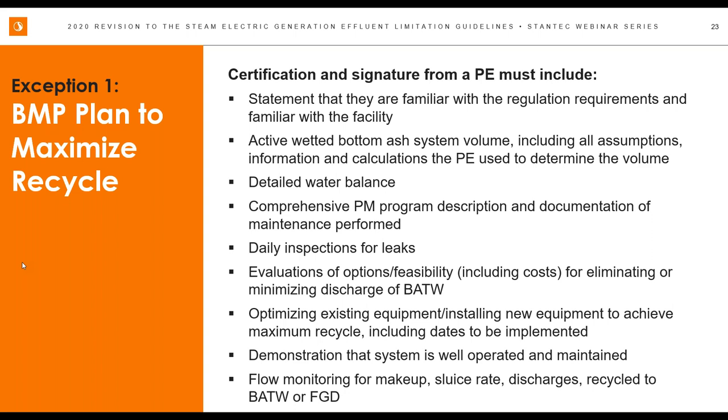a detailed water balance. And I would suggest here that the detailed water balance is not what you submit on your NPDES permit. That is a very high level water balance, and I would not say that is the level of detail that you would need here. This would be a water balance around your bottom ash transport water system.